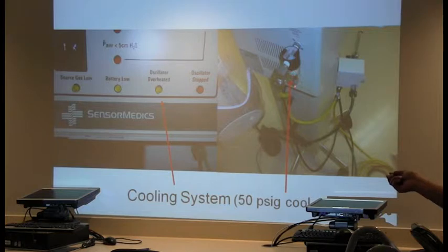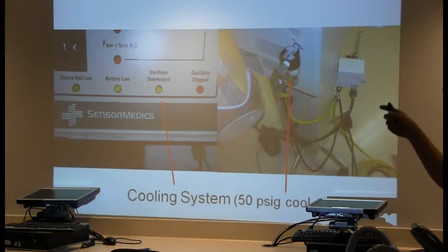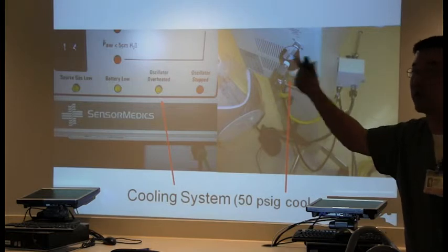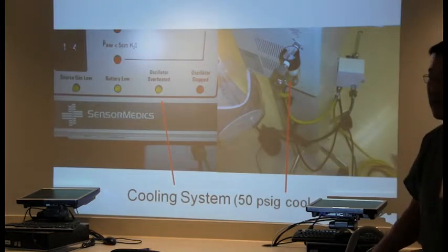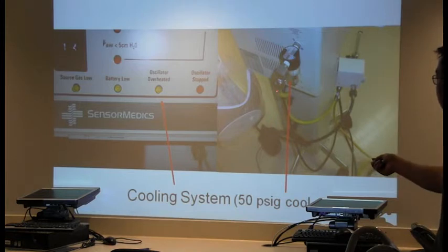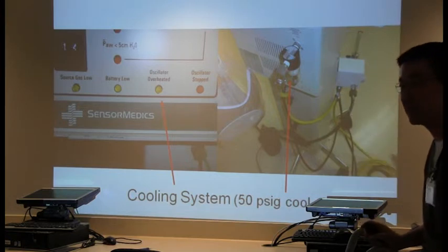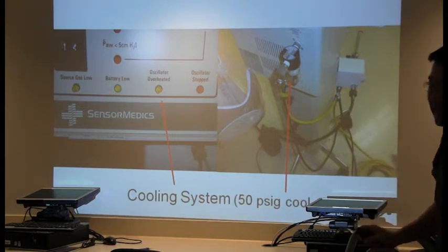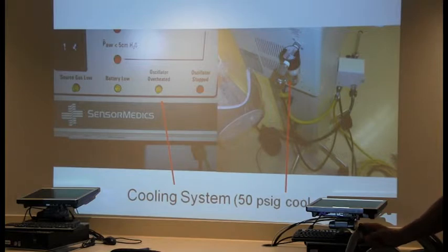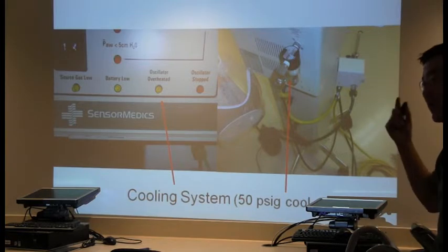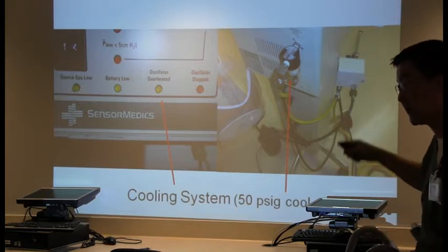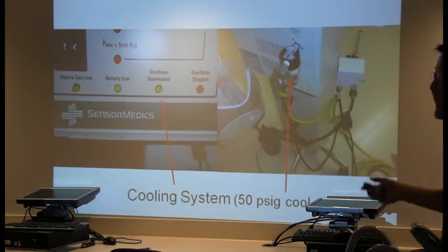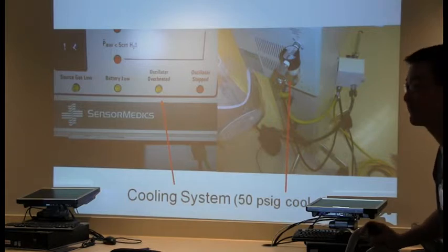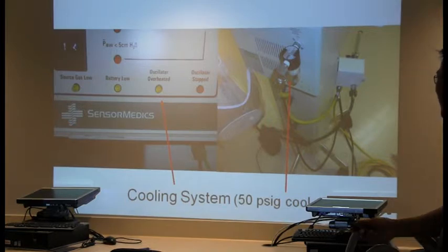But I'm really surprised that it will go in here, because this means that the wall system has moisture in it. And that's a big concern. Yeah, because if you look at the line, this is your air line. That'll kill all that. So something's contaminated in the system, because you're not supposed to have moisture in the system. You have to notify the hospital engineer. So next time that happens, let me know, so that we can inform the proper engineering staff to go take a look at the air compressor, because something's leaking in the system and it shouldn't be. It should be dry. Now you know. Good. All right.